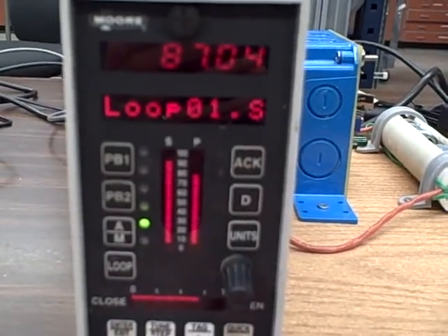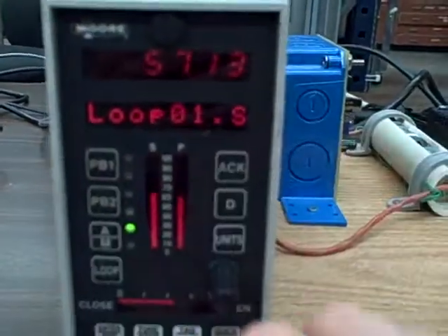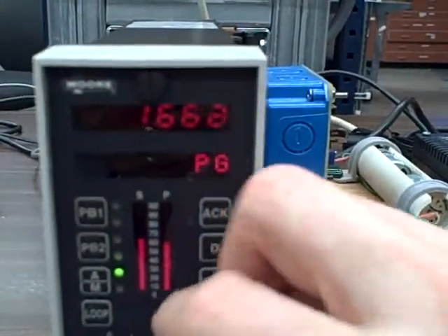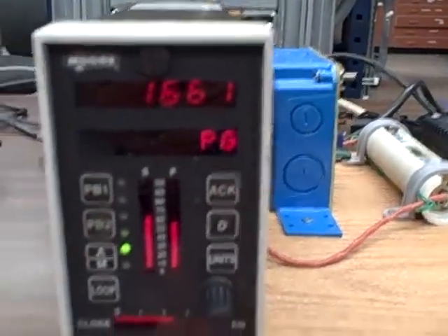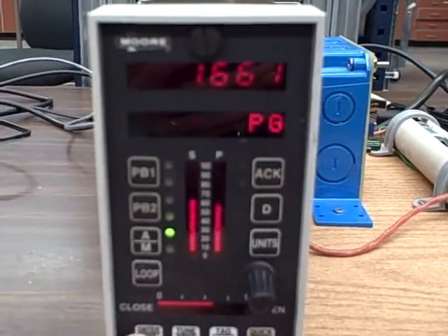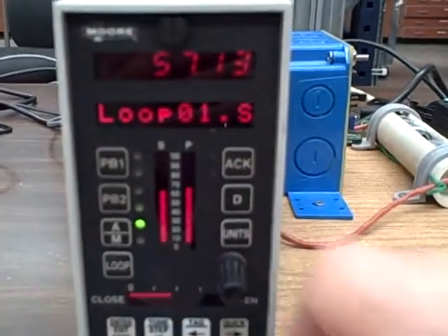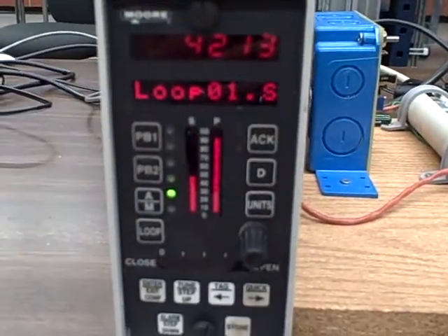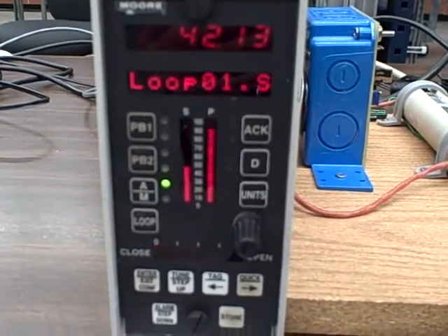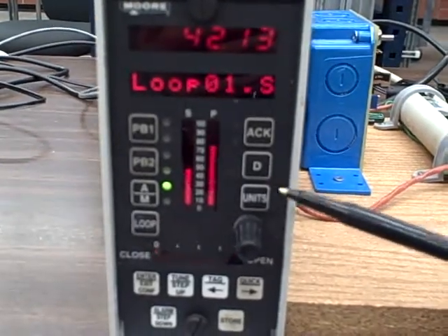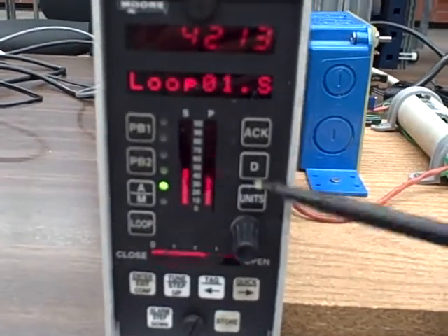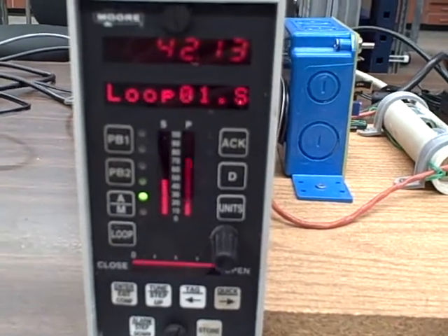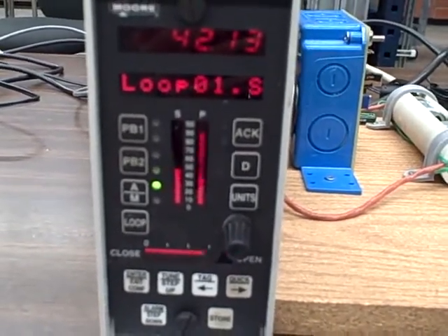I can adjust the gain up even further if I wish. Go back to my tuning button. Let's say I move the gain up to 1.6, and I store that value. Well, at this point, if I make a set point change, we can see right here, the loop became unstable without me even making a set point change at all. We have so much gain in the system now, it completely overreacts and is unable to hold the process variable at set point or even hold it steady at any value. This is a very poorly tuned control loop.